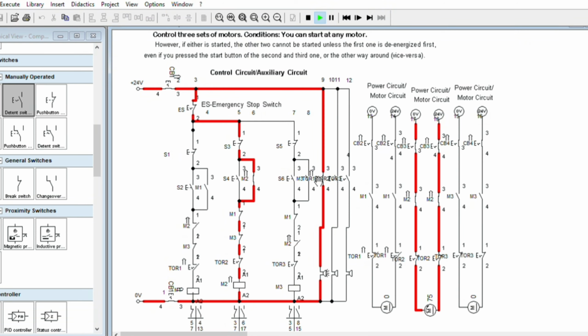You can also design that if one TOR, if one motor is in trouble, the other two cannot operate. That means you will use one overload relay, if the motors are identical and they are not in operation at the same time. If the motors are identical, you can use one overload relay. If there are three motors of different sizes, use three different sizes of overload relay. Again, do not reset but turn off the circuit breaker. In some cases, it will keep memory here. That software will sometimes do that, but that's fine. Turn that off.